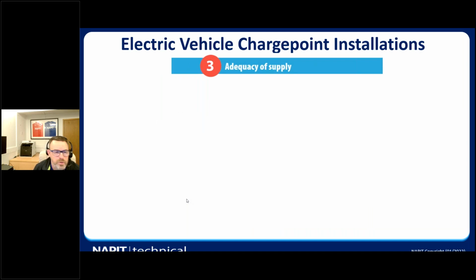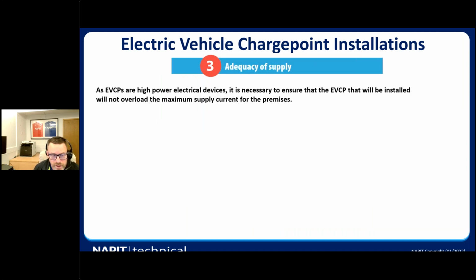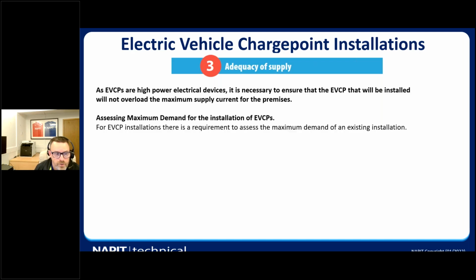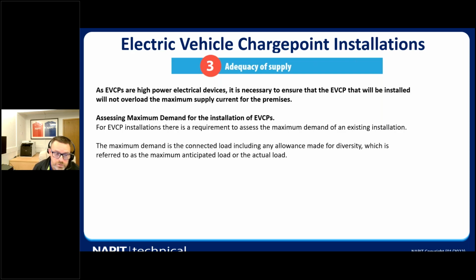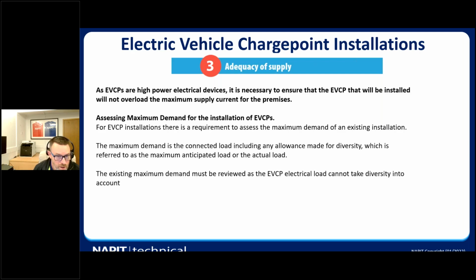Next one we're looking at is the adequacy of supply. Now, electric vehicle charge points are high power electrical devices, and we need to make sure the EV charge point is installed and won't overload the maximum supply to the premises. So what we need to do is assess the maximum demand for the EV charge point and the installation. So we're looking at the installation, what's the maximum demand for the existing installation. Once we've assessed that, we need to make allowance for diversity, which includes the maximum anticipated load or the actual load of the installation. So this must be reviewed as the EV charge point can't take into account diversity of the existing installation.